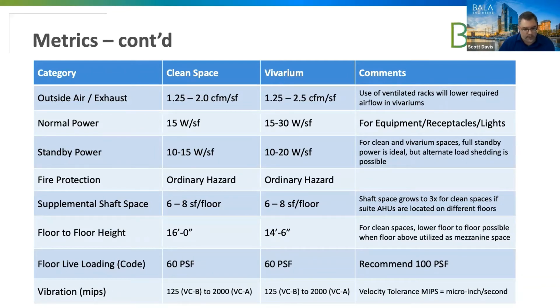It is possible to utilize the space above the clean room area. So if we use the bottom floor for the clean room, we can use the floor above it as a mezzanine MEP type space where we can fit all this equipment. You know, similar to the horizontal chase concept, the downside is it will eat up available rentable floor space. So again, it's a trade-off, but at the same time, you are able to get a clean space into a low floor-to-floor height. So it's, again, trading off your needs and the available space you have to work with and what the program dictates.